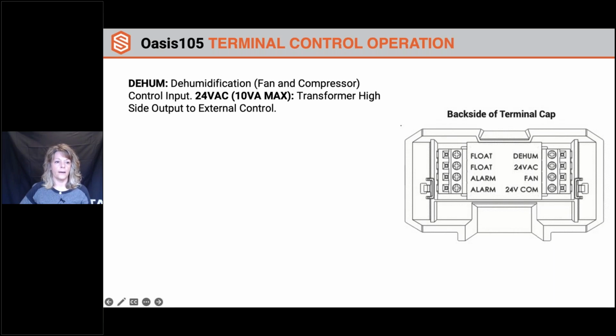We've got several different relay inputs here. 24VAC, so we're at about 10VA max for this unit. So you might have to utilize something else if there's not enough power to control additional components beyond this external control. Basically, this controller is to wire an external controller, and that's about the max power it has. If you want to use other components like a ventilation damper, you're going to have to wire that to the HVAC source, which is different than our other Ultra units. You need to be aware, and that is in the manuals on how to do that for this unit.